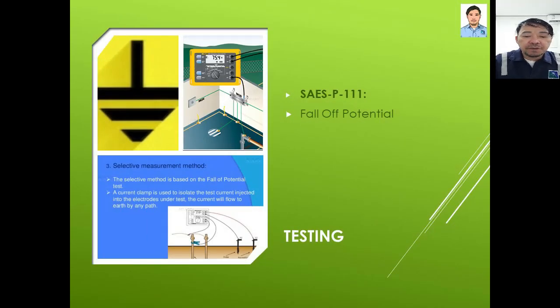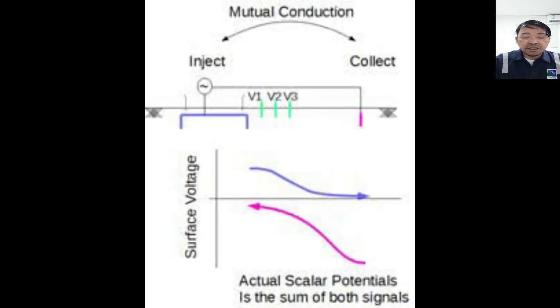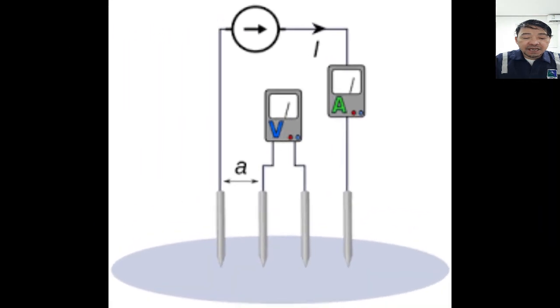Step touch potential and measurement of earth resistivity. This has been done during the design stage. For substations having equipment operating at a nominal system voltage exceeding 1 kilovolt, a ground grid meeting the requirements of IEEE 80 for step and touch potential shall be installed. Measurements of earth resistivity and ground impedance shall be made in accordance with IEEE 81 or by a non-contacting ground resistivity mapping instrument.